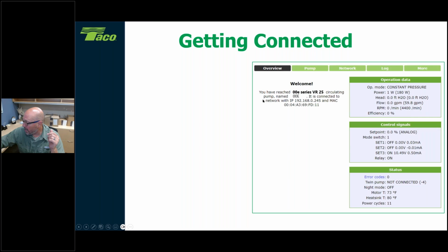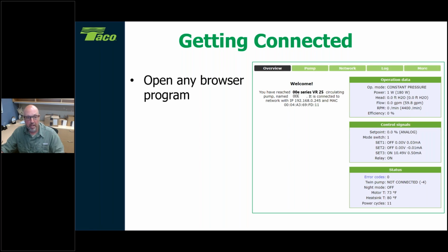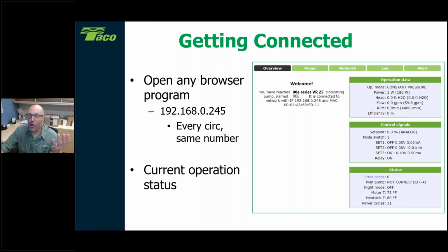All right, so once you tie in, this is the screen that pops up. It just says welcome, you're connected to whatever size circulator you have, named 00E, and it gives you the operation mode. Right now this circulator is powered down, and this shows what is happening at the moment. The circulator is set up in constant pressure mode. It is not spinning, but the power head is powered, so it's only consuming 1 watt out of a maximum for this model size of 180 watts. Flow, head, RPM, efficiencies, and your signals coming in, and no error codes. You're good to go. This is just your quick overview.